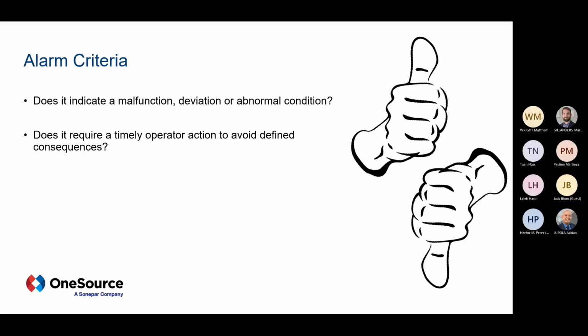So, alarm criteria. These next items that we're going to go through all need to be met before you actually go through an alert and create an alarm. If any one of them is not met, the recommendation is probably not to issue an alarm. The first of these is: does the issue indicate a malfunction, a deviation, or some type of abnormal condition? If not, it isn't recommended to make that an alarm. Second is: does it require a timely operator action to avoid consequences?